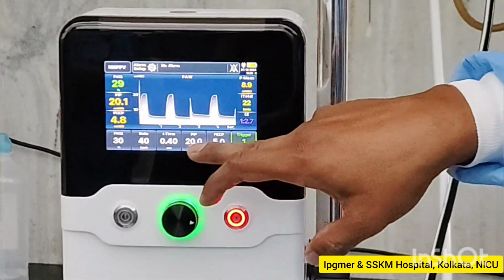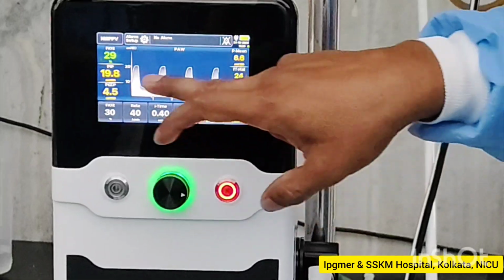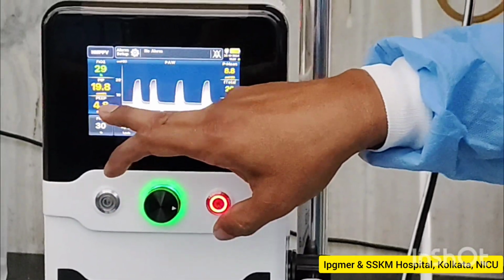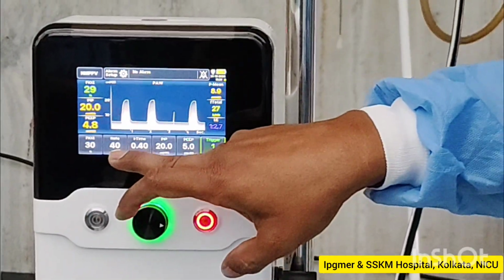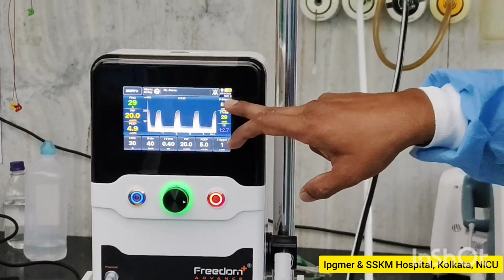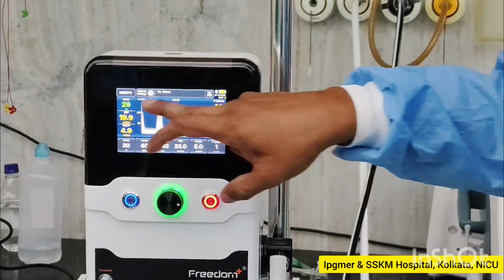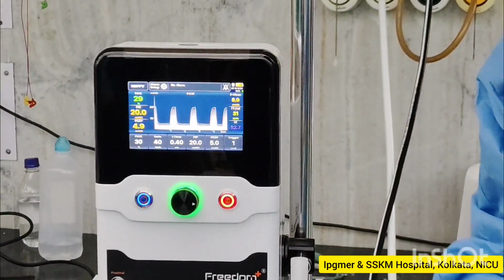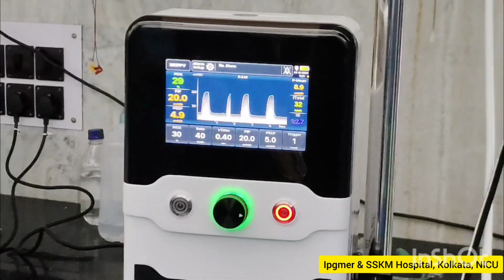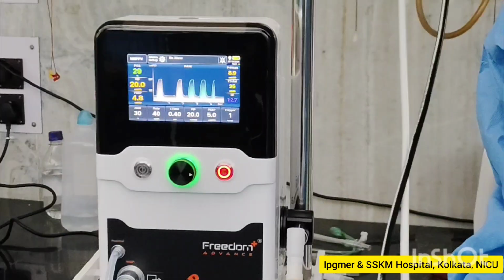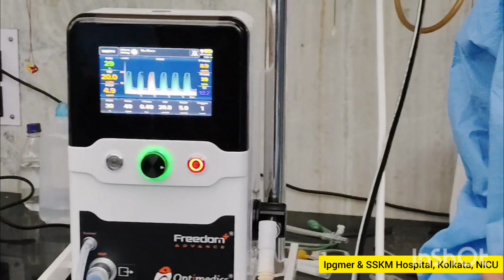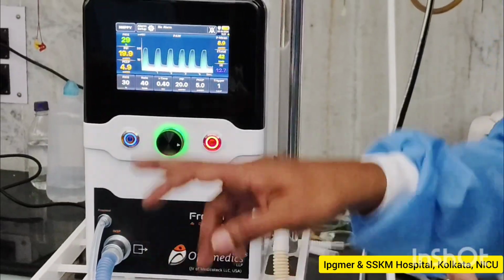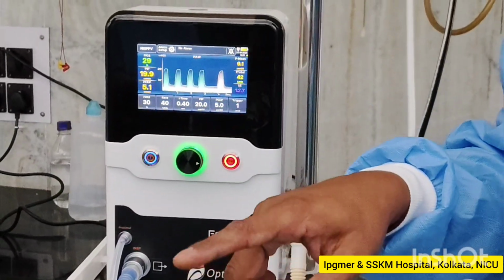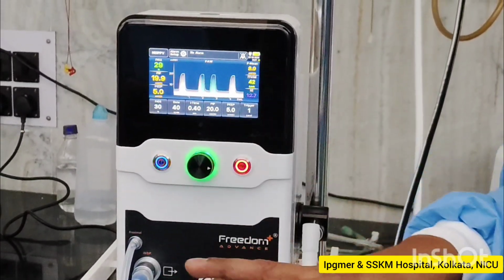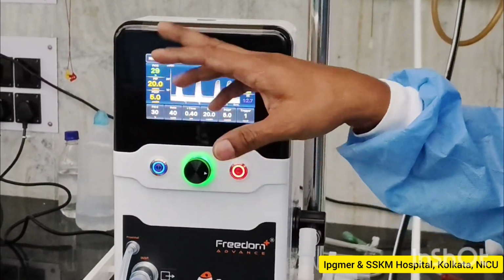Whatever the set parameters are, they are delivered. So PIP and PEEP are 20 and 5. The machine measures between 19.7, 19.8, and 4.8. The rate is 40. It is increasing the rate. This is your mean pressure. This is your I ratio. This is your FI ratio. So right now the patient is not breathing. If the patient starts breathing, each and every time the machine will synchronize. The color will change. If there is a blue color, you can understand that's a patient-initiated breath, that's a synchronized breath. If the color is white, you can consider it's a machine breath.